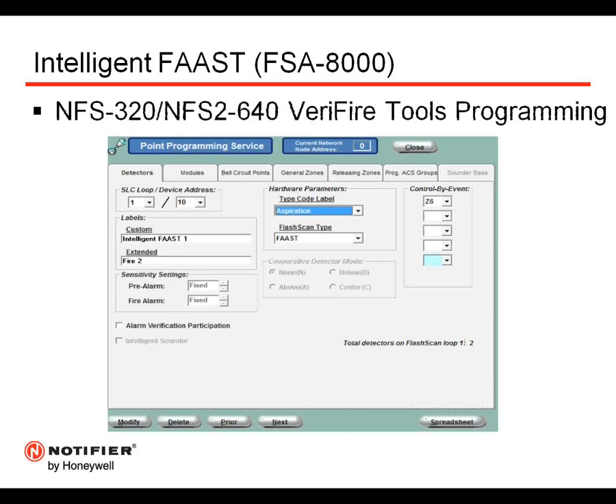And just a little bit on programming. Here's a screenshot from VeriFire Tools version 7.00. You can see where we can set up the aspiration type code. The flash scan ID is going to be FAAST. We can see that the cooperative detection and the sensitivity settings are grayed out because the sensitivity settings are configured and programmed into the FSA 8000 using the PipeIQ. But we can also take each one of the addresses that are assigned to it and associate it with up to 5 detector zones or 5 control by event programming. So it truly does program and configure into the ONYX series panel as if they were 5 spot detector addresses.